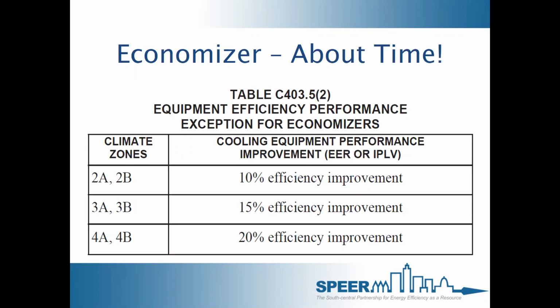I can't tell you how many HVAC contractors I've talked to, especially in the Houston area, who after they get their CO go disconnect the economizer. If the intent of the energy code is to save energy, we had to manufacture that economizer, ship it, install it, just to have it disconnected. I'd much rather have more efficient equipment on the building as an exception for the economizer.